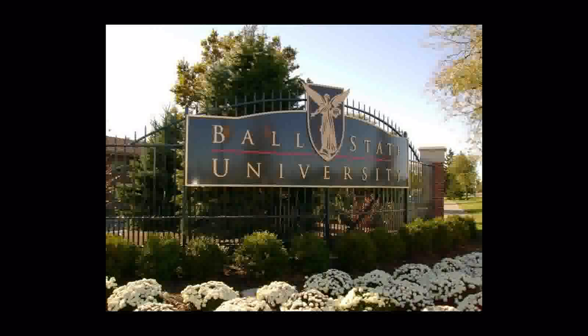To the how-do-we-adjust question, I didn't have time to go into it, but we are keeping our natural gas-fired boilers for several reasons. There are some processes on campus you can't convert to 150-degree water, so we need some steam for dining facilities. Plus we sell steam to Ball Memorial Hospital across the street—about 50% of their need is steam, and they can't go to 150-degree water. We'll have our gas boilers as peaking, so they'll be there to peak, as well as if we find we're inserting too much heat into the ground, I'll back away from the geothermal a little and make more steam for a certain number of buildings on campus. That way we can reduce the thermal energy flow into the ground.